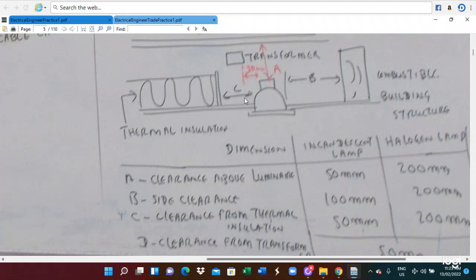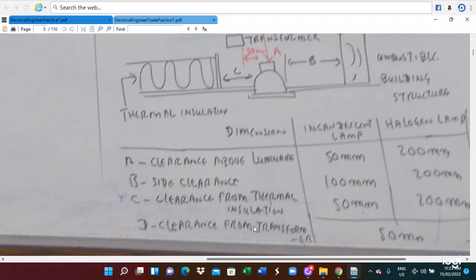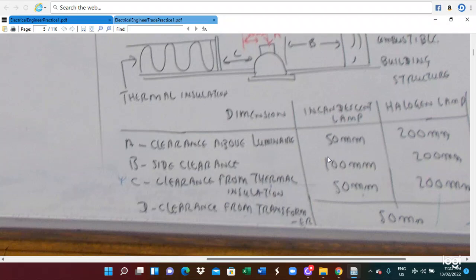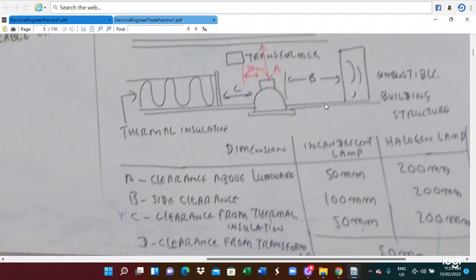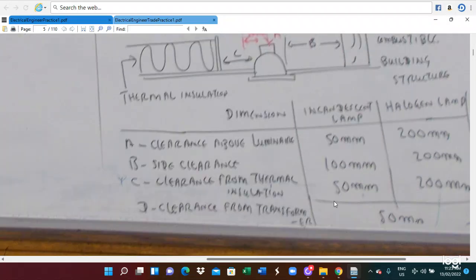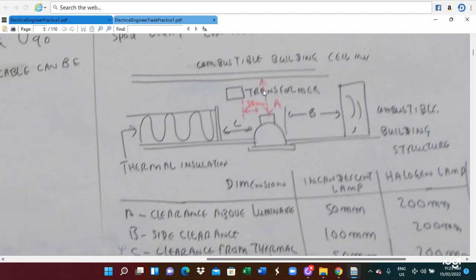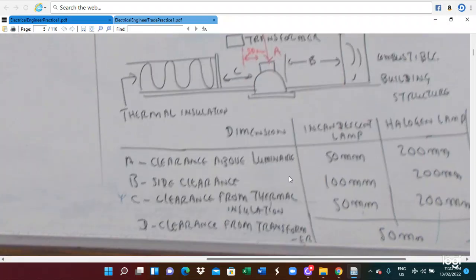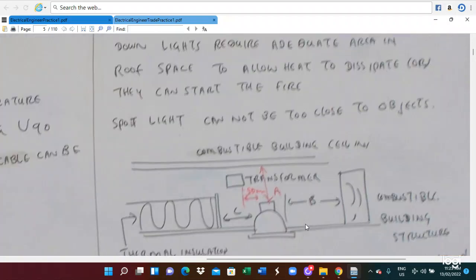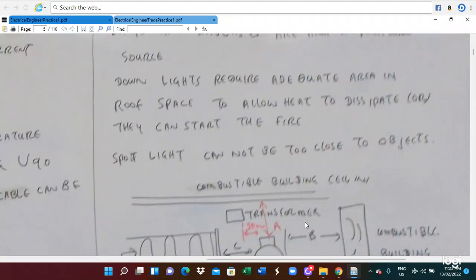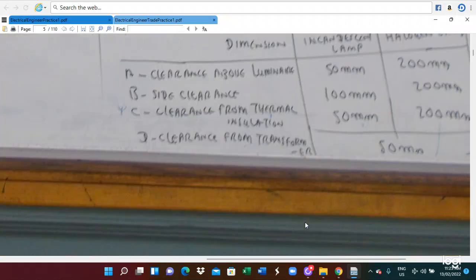Here C is clearance from the thermal insulation. That will be 50 millimeter for incandescent, and 200 millimeter for halogen light. D is clearance from the transformer. If you use a transformer, the clearance is also D, which means about 50 millimeter minimum. So this is an important aspect of appropriate clearance. When we are installing the light, appropriate clearance from the ceiling and from the equipment is also important. So we have to apply this at this stage.